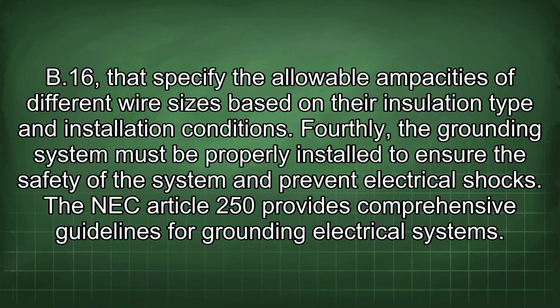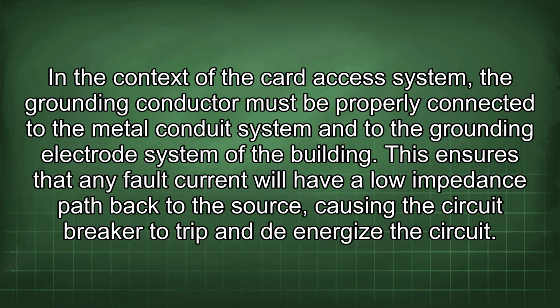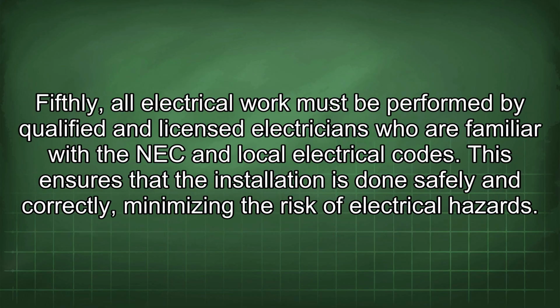Fourthly, the grounding system must be properly installed to ensure the safety of the system and prevent electrical shocks. The NEC Article 250 provides comprehensive guidelines for grounding electrical systems. In the context of the card access system, the grounding conductor must be properly connected to the metal conduit system and to the grounding electrode system of the building. This ensures that any fault current will have a low impedance path back to the source, causing the circuit breaker to trip and de-energize the circuit. Fifthly, all electrical work must be performed by qualified and licensed electricians who are familiar with the NEC and local electrical codes. This ensures that the installation is done safely and correctly, minimizing the risk of electrical hazards.